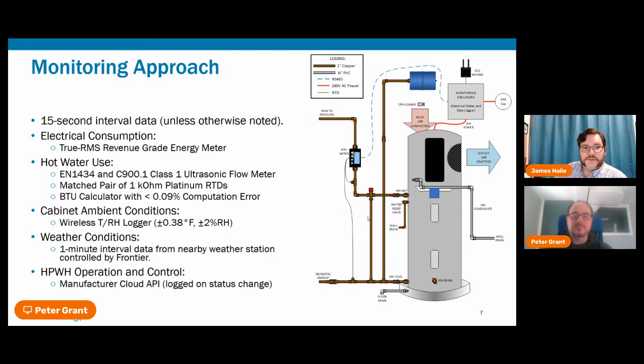One of the things that's drawn a lot of interest from this project is the airflow issues we encountered with the heat pump water heaters in the small cabinet. You may have noticed back on slide 6 that the air exhaust wasn't pointed directly at the louvered door. This was in keeping with the diagram and instructions in the installation manual, at least as both the designer and installer interpreted them. If that interpretation was wrong, it's worth noting that knowledgeable people looked at it and came to the same conclusion.